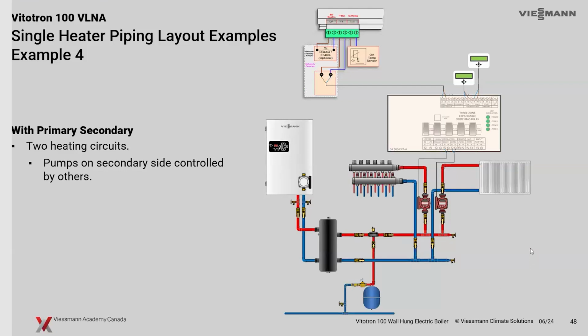And different but the same, we have zone pumps here instead in this application. What we're looking at here is using some sort of a zone box, some type for the pump modules. We're not going to use that secondary pump output inside of the boiler because we have two separate pumps here. We only want these pumps to operate whenever their specific thermostats are calling.